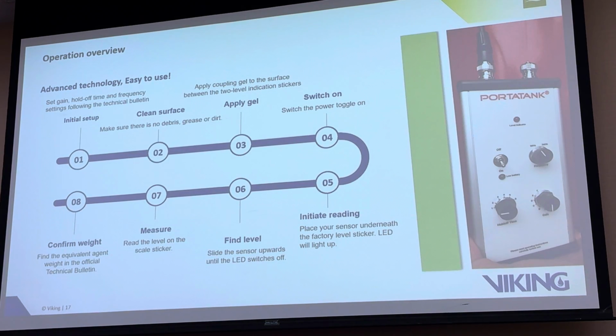So how does it work step by step, in a nutshell? The first thing you have to do is the initial setup with your device. You set the hold time, frequency, and gain, these three knobs. The manual tells you exactly, based on your cylinder and your agent, what settings you have to put.